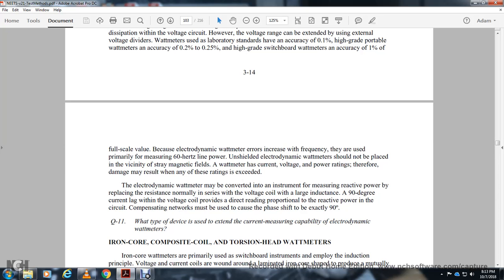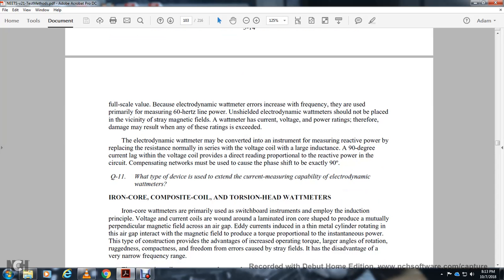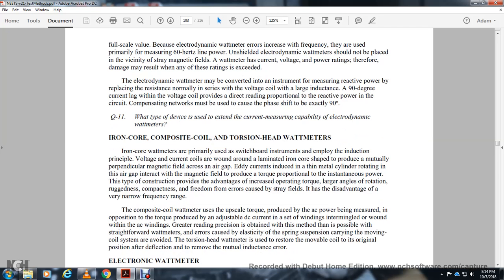The electrodynamic watt meter should be shielded and should not be placed in the vicinity of strong magnetic fields. The watt meter has current, voltage, and power ratings; damage may result when any of these ratings are exceeded. The electrodynamic watt meter can be converted to measure reactive power by replacing the resistance normally in the voltage coil with a large inductor to produce a 90-degree current lag, making the reading proportional to reactive power.